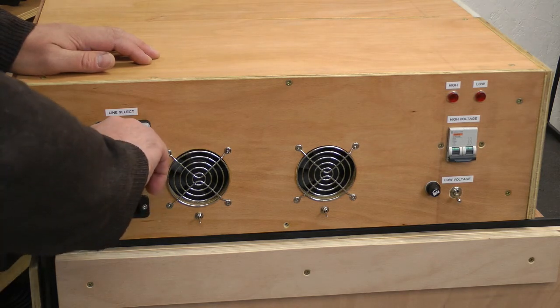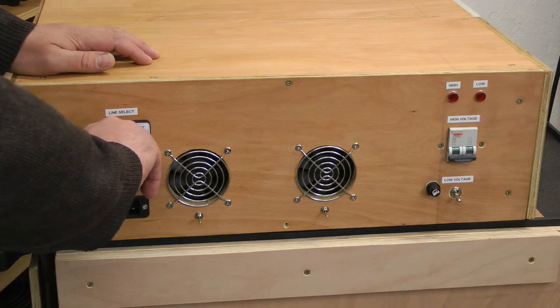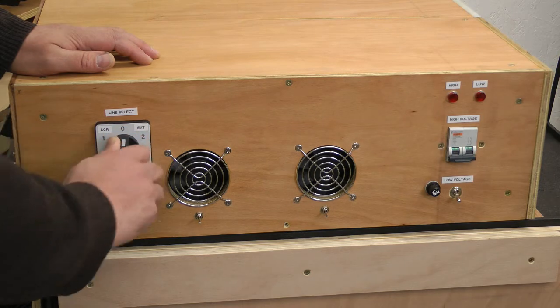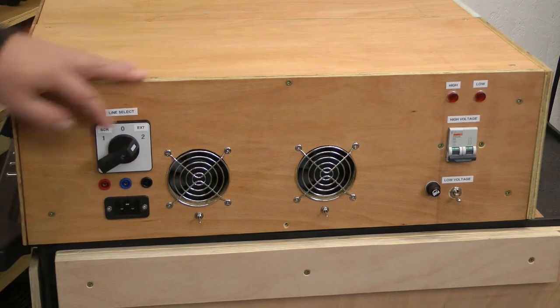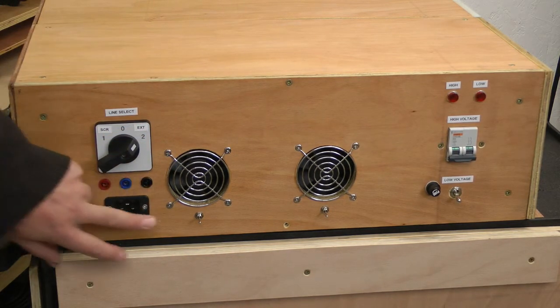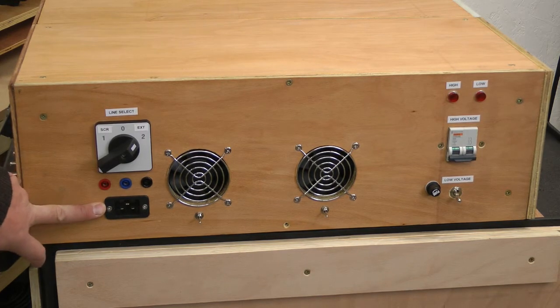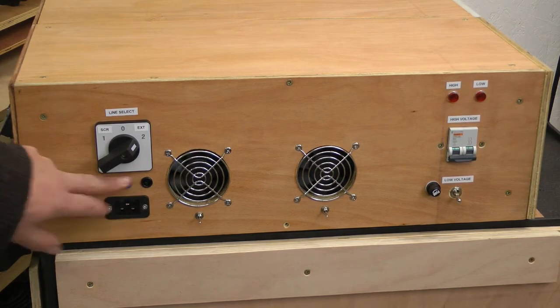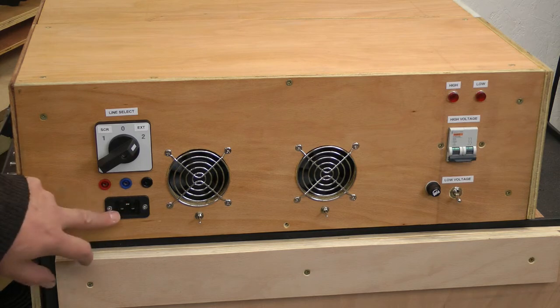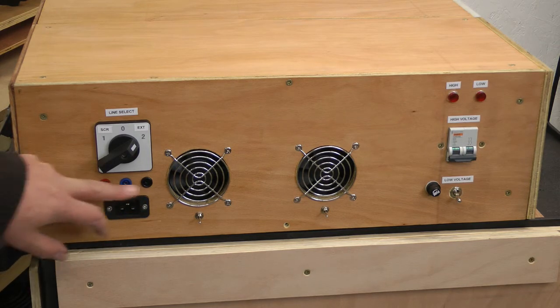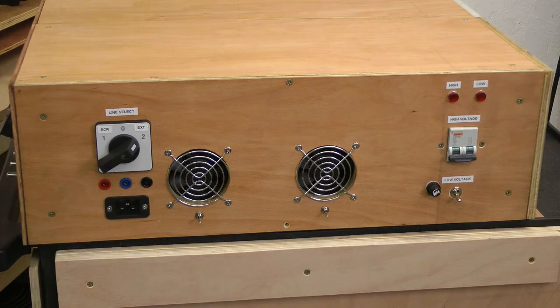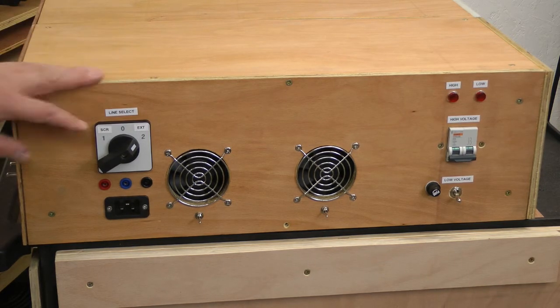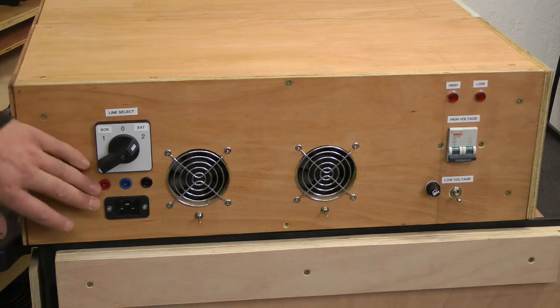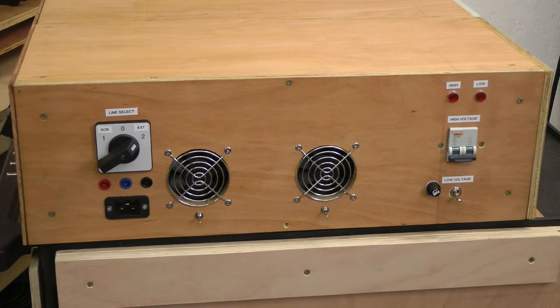So back to 0, if you put it to position 2, which is external, you can actually then feed power in via these terminals. They are connected together, so there's either a line input terminal or you can use the high voltage 4mm high voltage connectors as well.